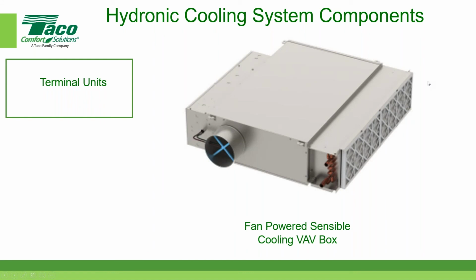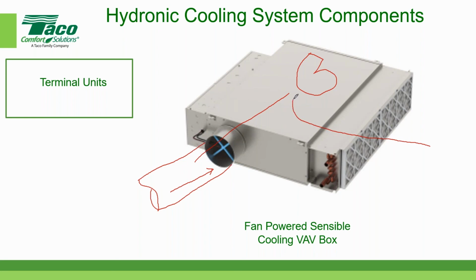Here's another terminal device a lot of people are not familiar with. This is called a fan-powered sensible cooling VAV box, variable air volume box. And this coil right here mounts in the side, airflow comes from the primary air duct. So here's the primary air duct. Kind of pretend there's a duct over here connected to this side. And that comes typically from your dedicated outside air unit, which is called a DOAS. And then there's a fan inside here. You can't see it, but I'll kind of draw it, kind of imagine the fan is lying on its side. And so it has the primary air, it mixes with the ceiling air and gets cooled by the sensible cooling coil, and those two air quantities mix and it comes out the end of the VAV box.